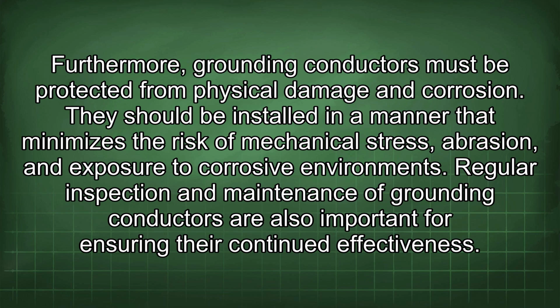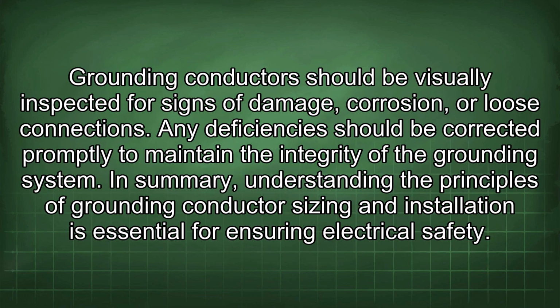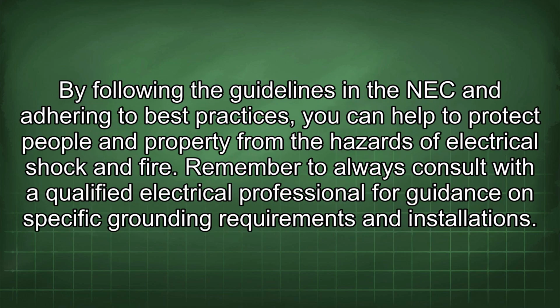Regular inspection and maintenance of grounding conductors are also important for ensuring their continued effectiveness. Grounding conductors should be visually inspected for signs of damage, corrosion, or loose connections. Any deficiencies should be corrected promptly to maintain the integrity of the grounding system. In summary, understanding the principles of grounding conductor sizing and installation is essential for ensuring electrical safety. By following the guidelines in the NEC and adhering to best practices, you can help to protect people and property from the hazards of electrical shock and fire. Remember to always consult with a qualified electrical professional for guidance on specific grounding requirements and installations.